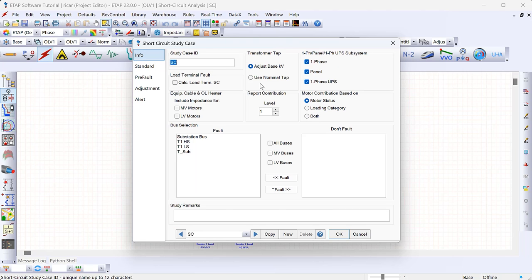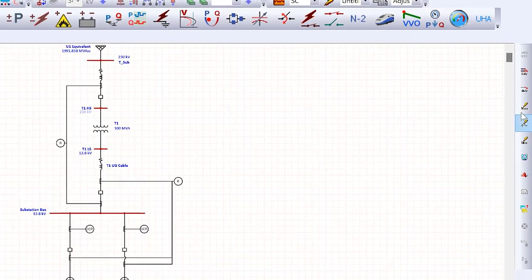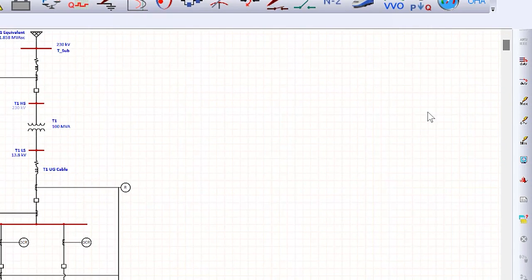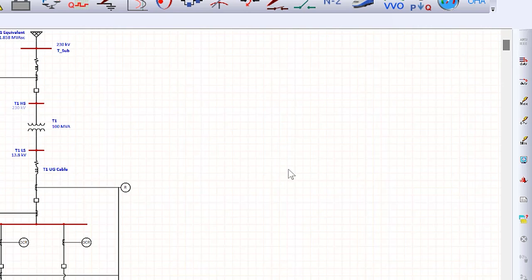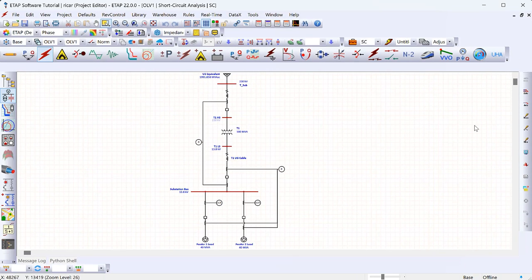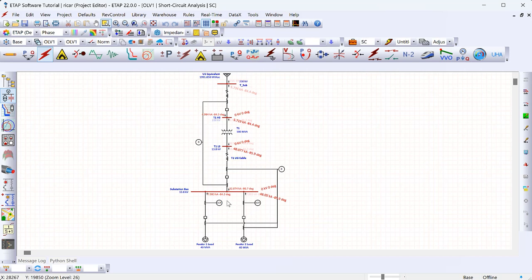There are many options here; typically you don't have to change them unless you need a specific standard like IEC instead of ANSI. I'm going to leave all of those at default and just make sure all buses in the system are faulted. Clicking OK takes us back to our model, which is blank because we haven't run the short circuit study yet. When you select 'Maximum', ETAP uses the sub-transient reactance for any synchronous generators and accounts for motor contribution during the first few cycles of a fault. Clicking 'Max' now, ETAP runs the short circuit study and you can see contribution coming back from the motors.